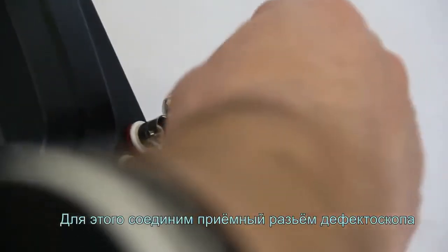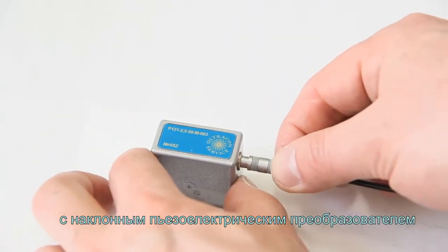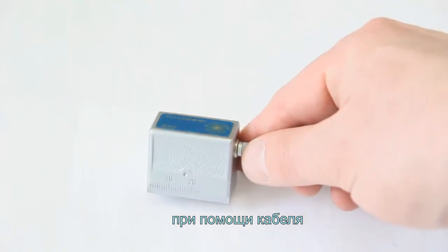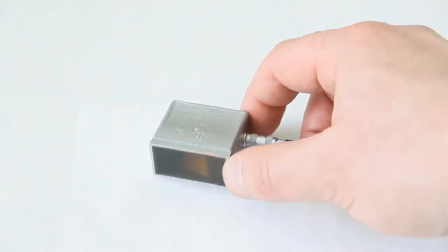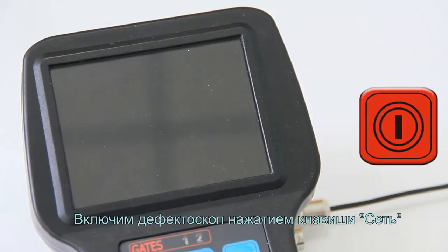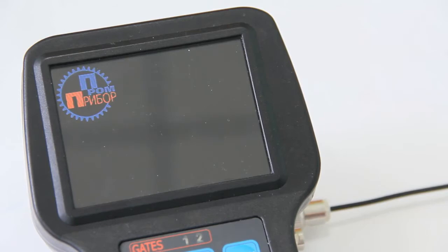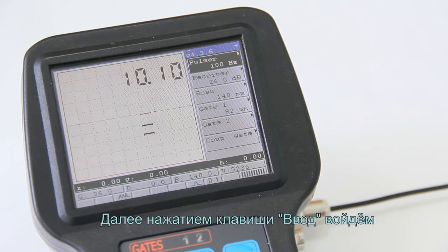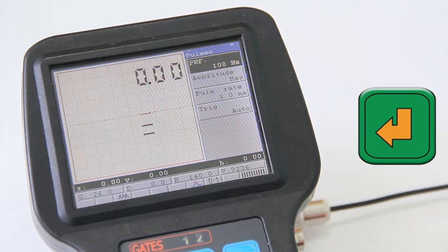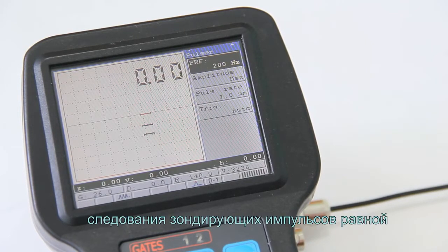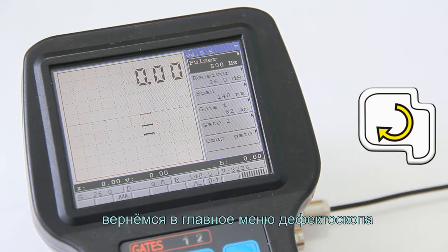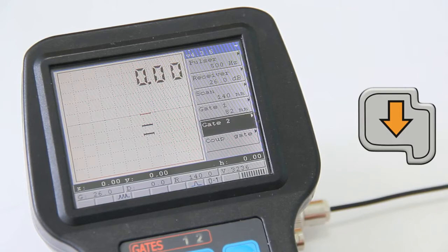Calibration of angle beam piezoelectric probe. Firstly, connect the angle beam probe to the flaw detector connector using the cable. Use power button to switch on the flaw detector. Then by pressing the Enter key, enter the pulser menu. In PRF menu item, set the initial pulse repetition frequency that equals to 500 Hz. Then using the Return key, return to the main menu of the flaw detector.